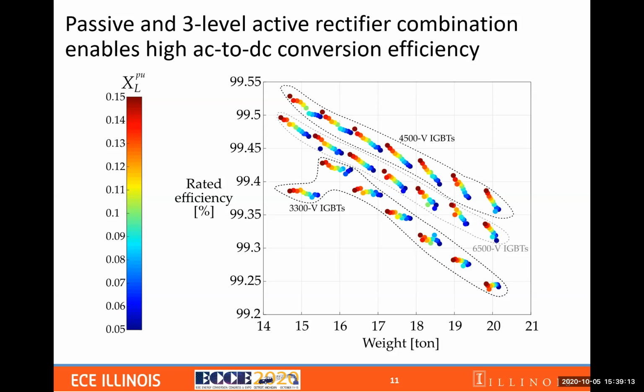And the second trend is that within each group of IGBT, a lower weight will give you better conversion efficiency. That is kind of counterintuitive, because conventionally in power electronics or in machines, a heavier system is usually more efficient. So this is why: for the integrated generator rectifier system, the lower weight will correspond to a narrower speed range. A narrower speed range allows us to boost the DC side voltage to a higher value. And at a high DC side voltage, in order to deliver the same amount of power, you need less current. Because you need less current, your ohmic losses are reduced. That is the reason why you see lower weight here correspond to a higher conversion efficiency.